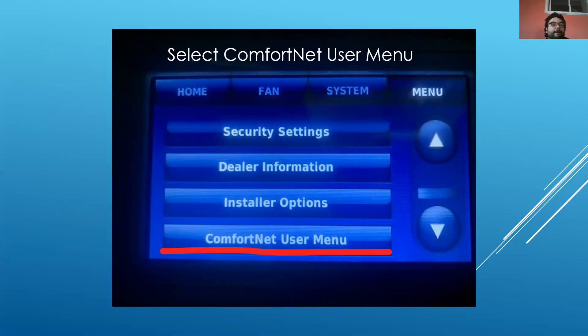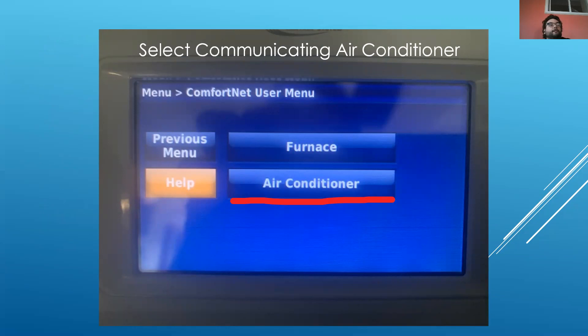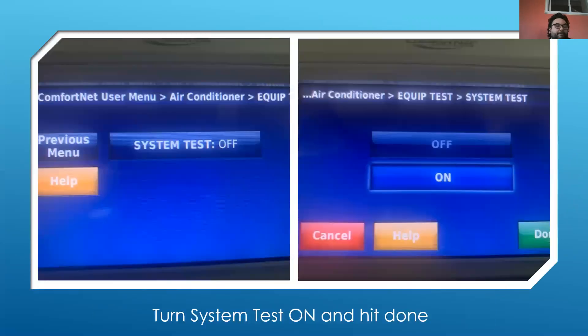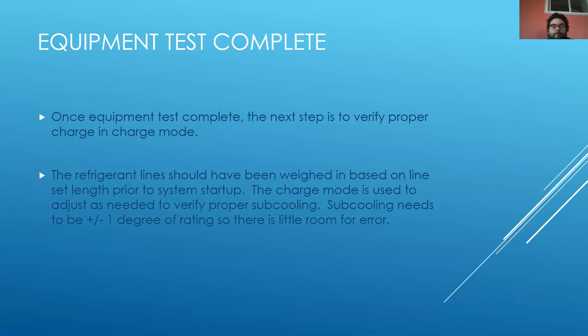Go to the Comfort Net user menu and select air conditioner — it may say indoor unit depending on the thermostat. Then go to equipment test under the Comfort Net user menu and turn the system test on. It will run for about 15 minutes for the full equipment test, checking sensors and making sure everything looks okay. I've been told by Daikin tech support that depending on the temperature outside, it could take anywhere from 15 minutes to an hour. A Daikin rep mentioned someone in Canada doing this test at negative five degrees outside and it took about an hour, so just be patient and wait until the test is done.